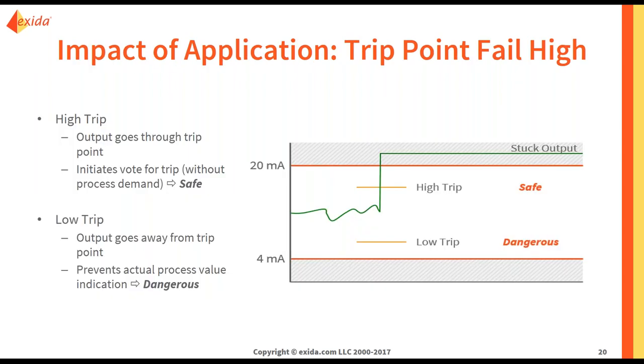Let's say your trip point is a high trip point. In this case, the output goes through the trip point for a fail high. This initiates a vote for trip without a process demand or a hazard to your system, and so this is a safe failure. However, if you have a low trip, the output goes away from the trip point. This prevents the actual process value indication, and this is a dangerous failure. Your plant is not tripping, but your safety instrumented function can no longer respond to the hazardous scenario.